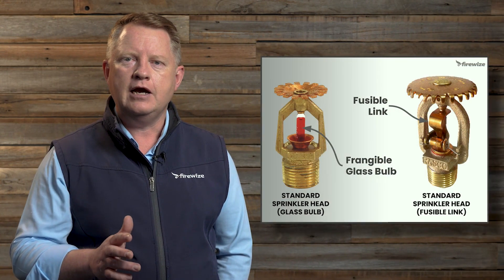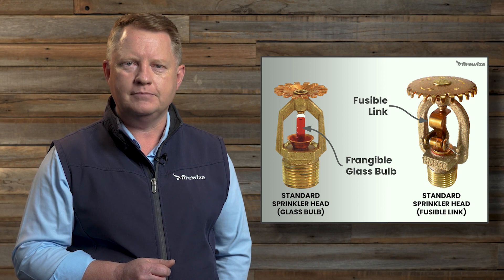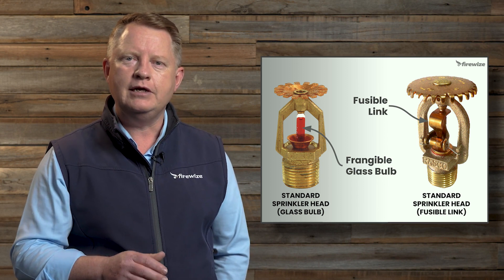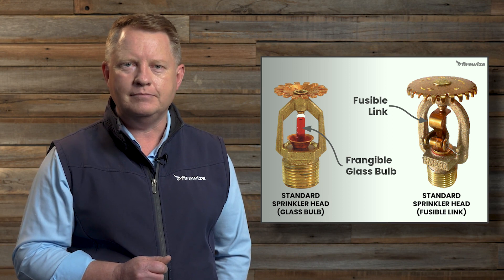In addition to glass bulbs used as part of a sprinkler head, another option you might see is a fusible link. A fusible link is a two-part metal element that is fused together by a heat-sensitive alloy. These sprinkler heads operate when the ambient temperature reaches or exceeds the activation temperature of the alloy. When the alloy melts, it releases the valve assembly. The operating temperature of these sprinkler heads is normally etched or embossed into the sprinkler head and may also be indicated by the same colour system as used for glass bulb type sprinkler heads.